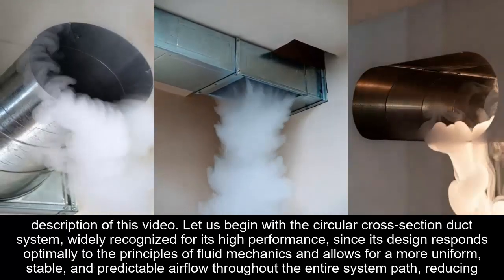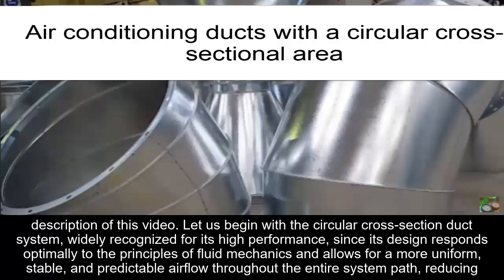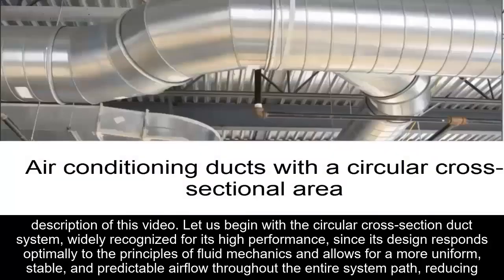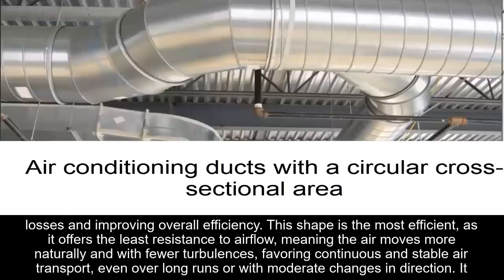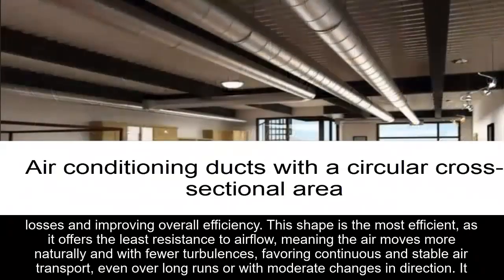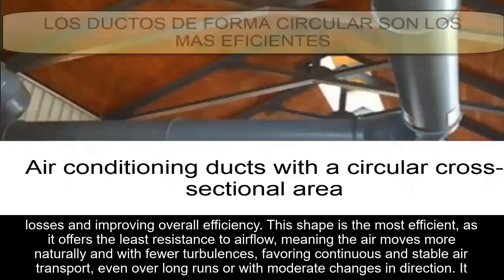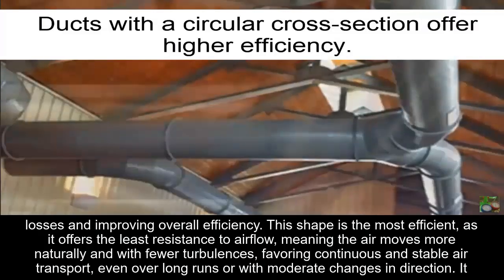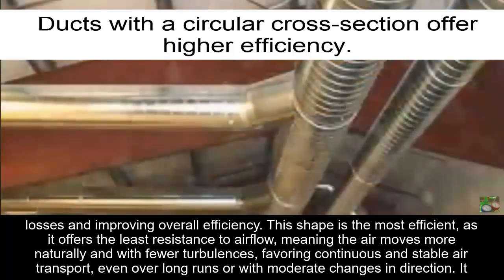Let us begin with the circular cross-section duct system, widely recognized for its high performance since its design responds optimally to the principles of fluid mechanics and allows for a more uniform, stable, and predictable airflow throughout the entire system path, reducing losses and improving overall efficiency. This shape is the most efficient since it offers the least resistance to airflow, meaning the air moves more naturally and with fewer turbulences, favoring continuous and stable air transport, even over long runs or with moderate changes in direction.